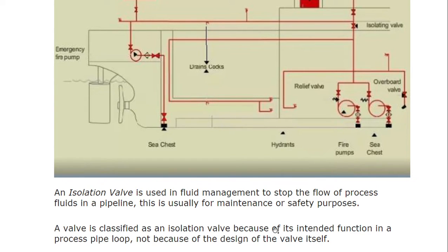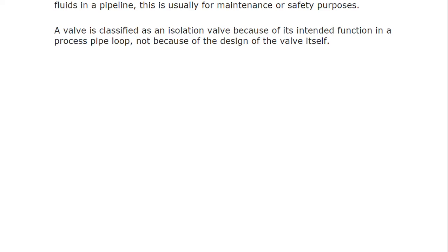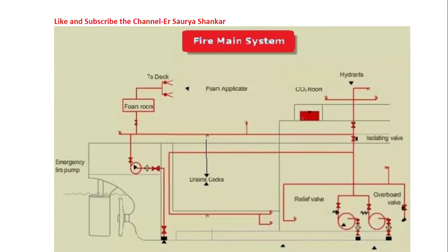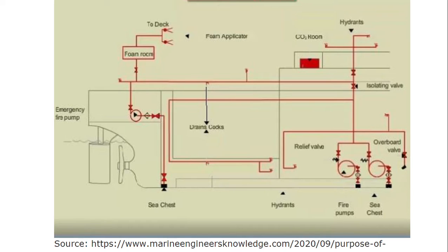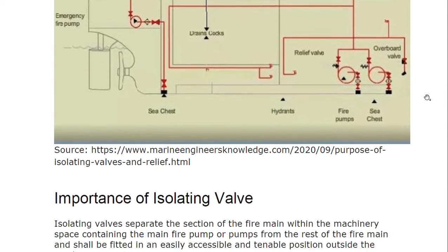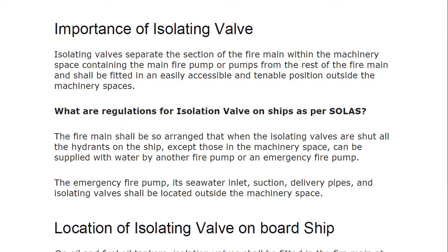The same diagram is being replicated, and you can see here that the foam system also gets supply from the fire main system. Now, the importance of isolating valves: isolating valves separate the section of the fire main within the machinery space — containing the main fire pump or pumps — from the rest of the fire main. They shall be fitted in an easily accessible and tenable position outside the machinery space. So when asked what an isolating valve is, the answer is it isolates the machinery space from the other spaces.